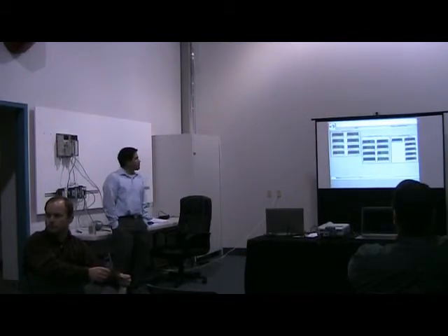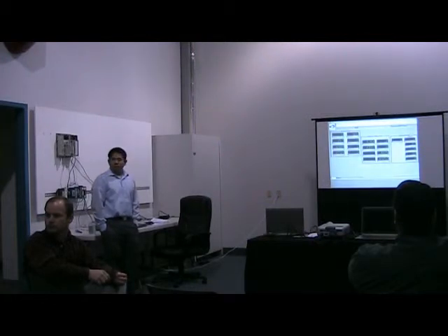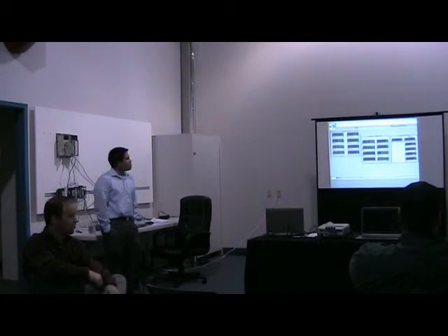And there's a bunch of PDAs now that have HART software that we use. Smart put out packages, and we've got PDAs that can do everything off of those nowadays. You don't even have to have the calibrator anymore. We have some old ones. You can adjust the calibration remotely.